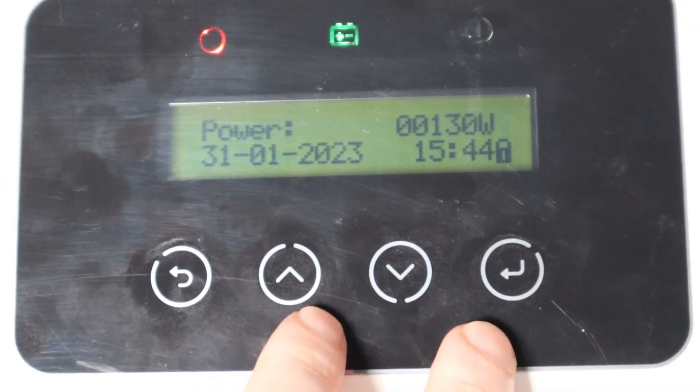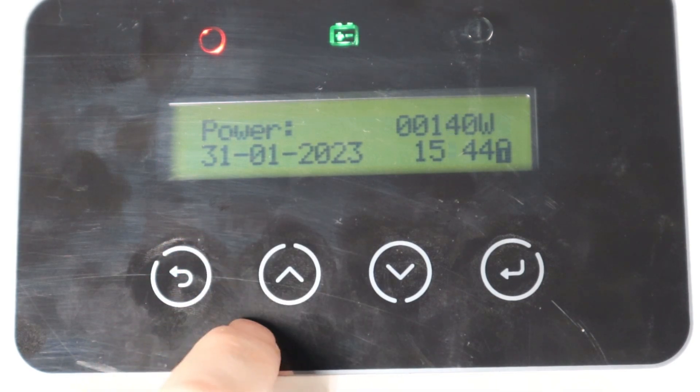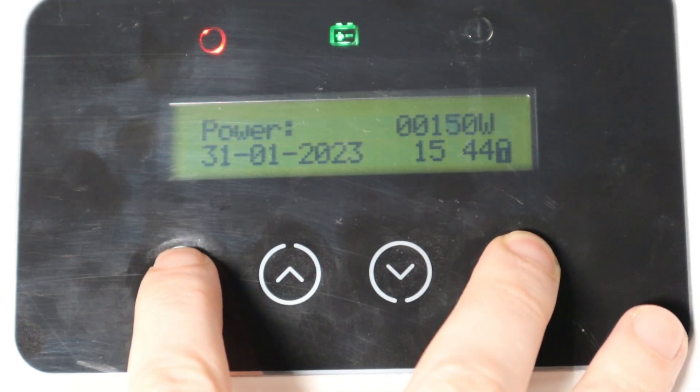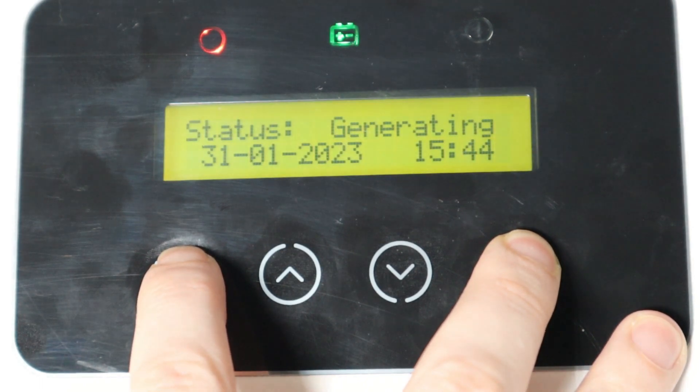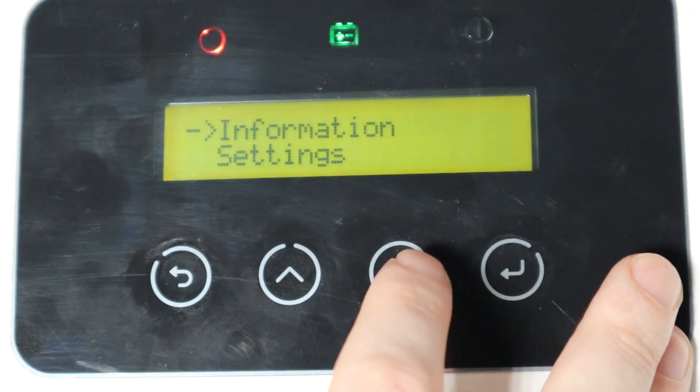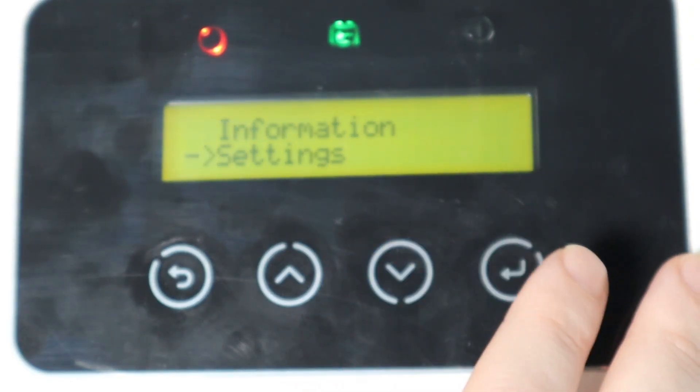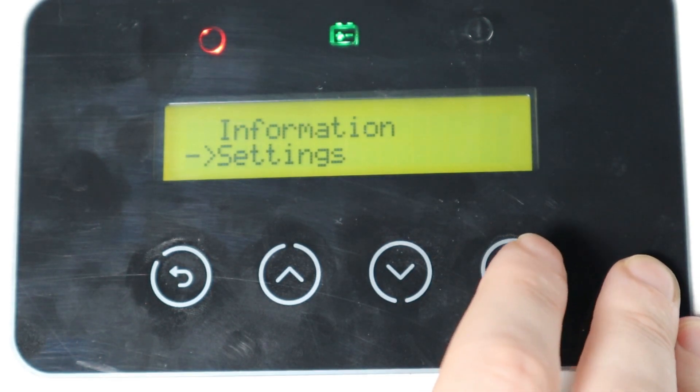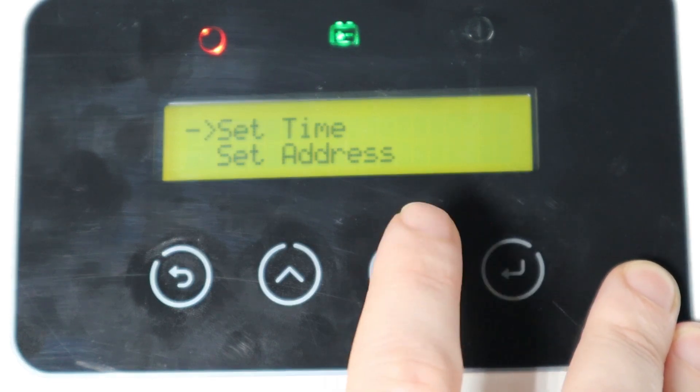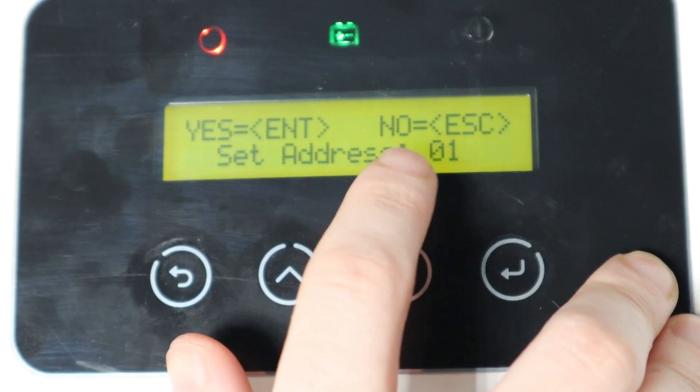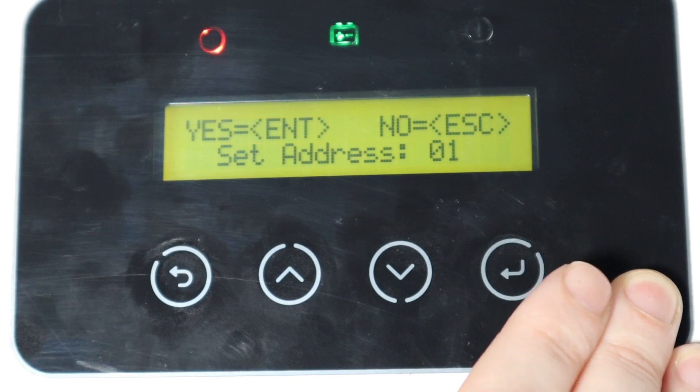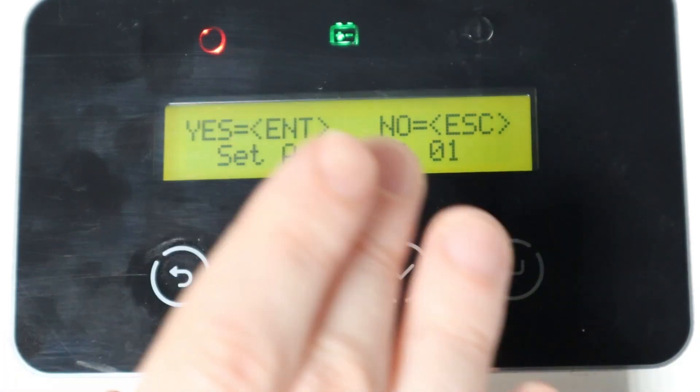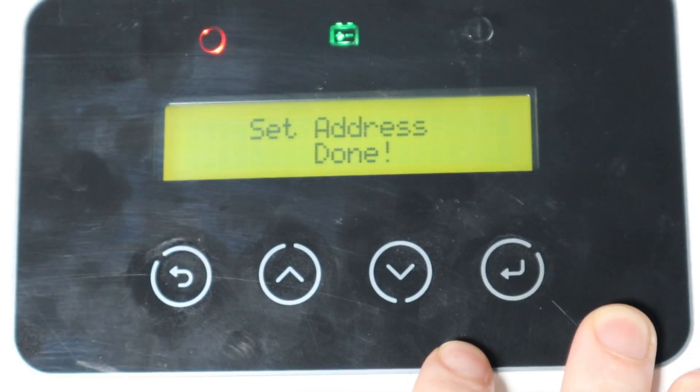Okay, one of the last steps to do on this system to get the EPM working is set up the inverters. So these inverters need to be addressed. So that's the first thing we're going to do. And the other thing they need to be is they need to have their fail safe enabled so that they are constantly looking for the EPM. And if there's ever not an EPM, they need to stop generating as in generate a fail safe event. So on each of the inverters, as I said in the beginning, you set them sequentially. So you go to settings, and then you set the address. So the default is one, and you would set this inverter to one, and then the next inverter to two, and the next inverter to three, if you had three inverters, you can't skip any numbers, and you have to always start at one. So you need one inverter at least set to one.